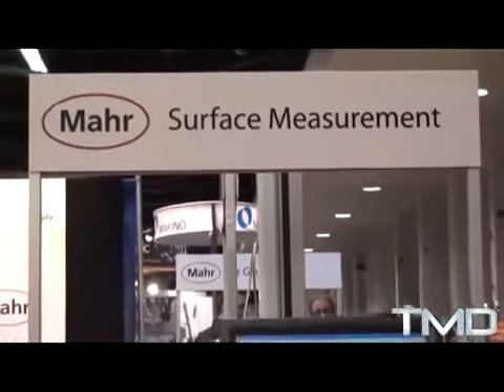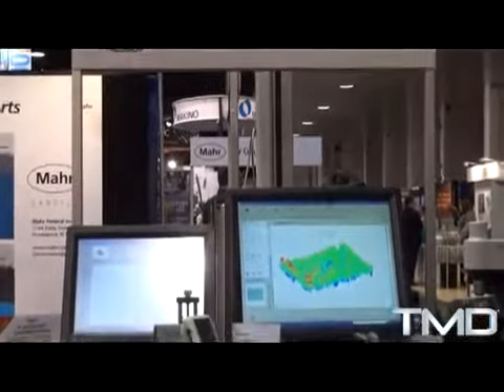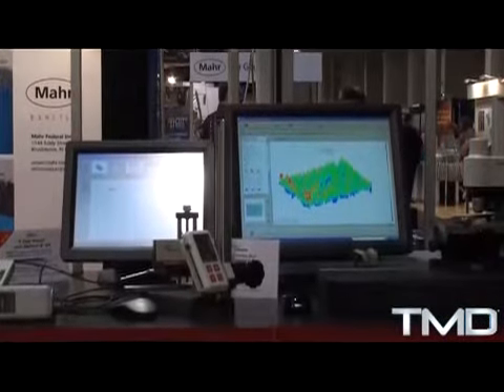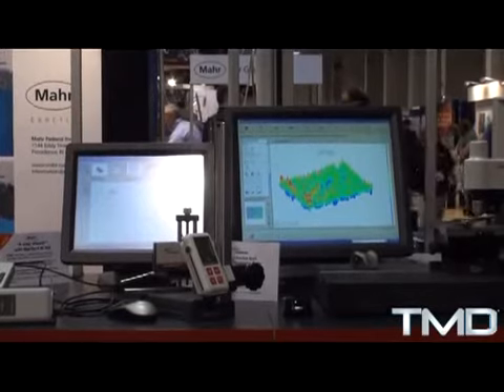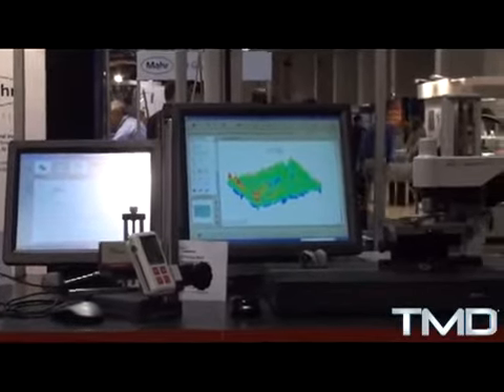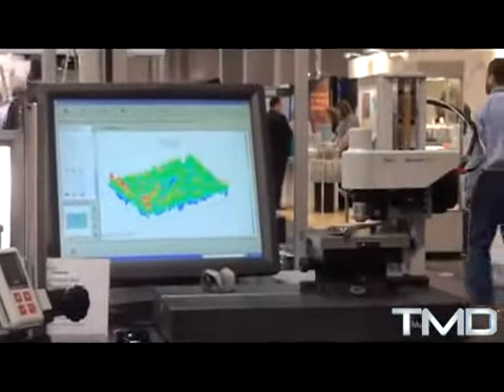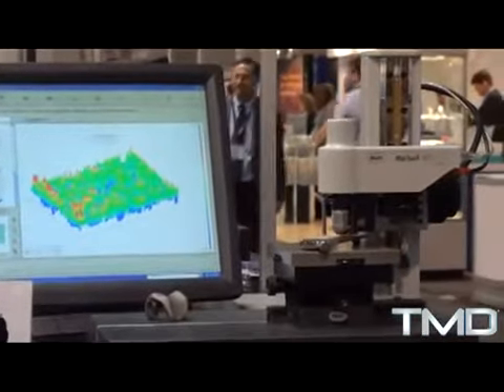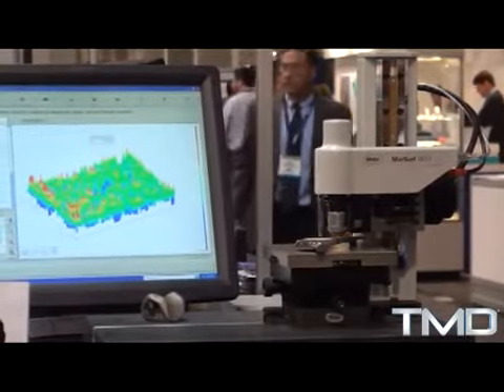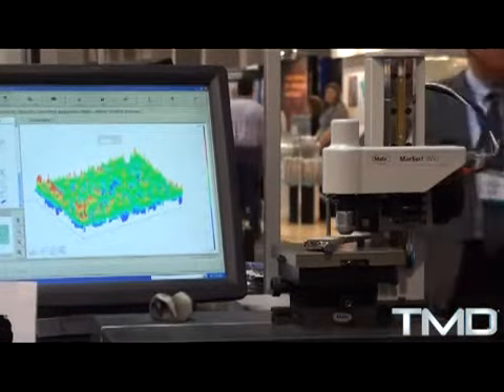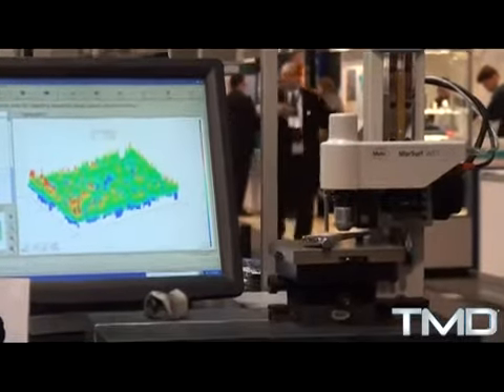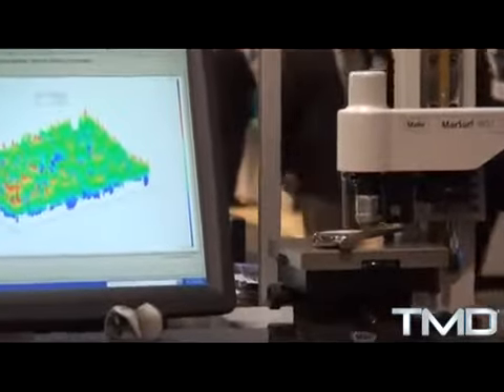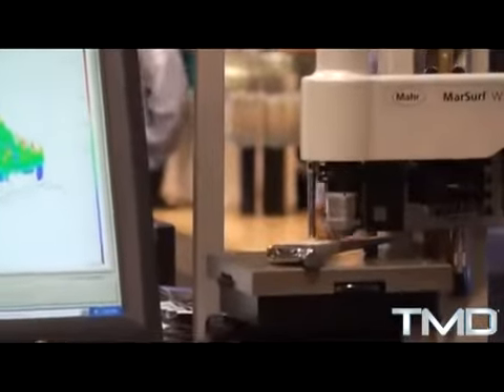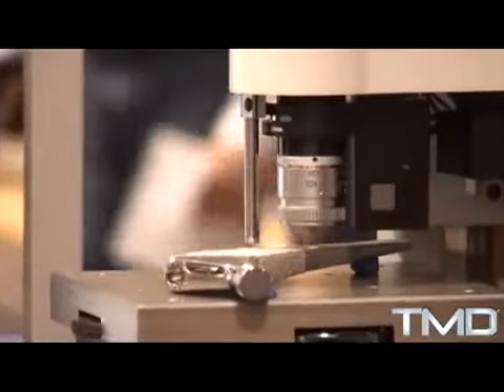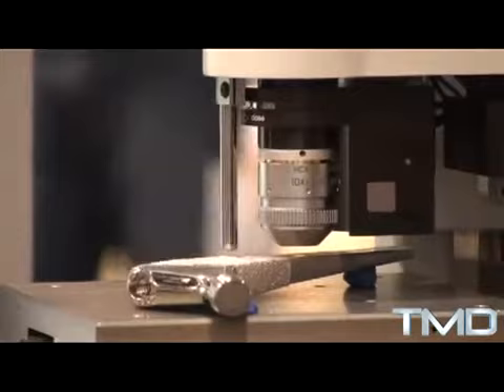This is our surface finish line, whether it's a portable skidded system or a more conventional machine with a skidless operation. On the right is the MarSurf TS50. It's a brand new system that allows you in about a 1 millimeter square area to pick up tens of thousands of data points in less than 1 minute and be able to do a three-dimensional topography analysis down to submicron level using white light interferometry. We see on the table there's an artificial hip component, and looking at the surface roughness configuration is a critical part, as well as the taper configuration as well.